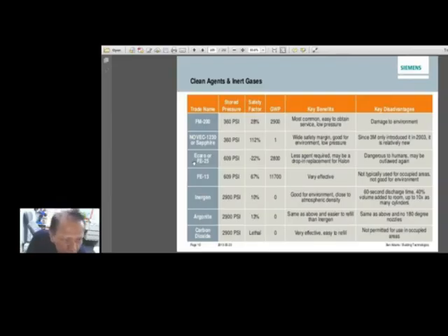ECARO or FE25, 609 PSI, so very high. Minus 22% factor, 2,800 for GWP. Less agent required, maybe a drop-in replacement of halon. So it says it is a possible replacement. Then dangerous to humans, maybe outlawed again.